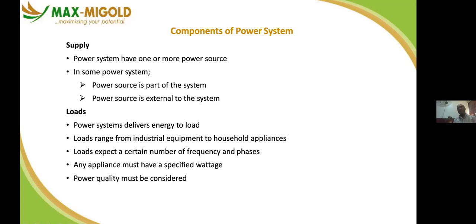Frequency also plays a major part in running your appliances. The power you are generating must maintain a certain frequency. In Nigeria, we make use of 50 hertz; in America, we make use of 60. It depends on the grid, which is standardized for use. So here in Nigeria, we make use of 50 hertz. Anything outside this range, between 49 and 52 or so, above or below, has an effect on your appliance. They will not work, or even if they are working, they won't work well. At times, they will not even come up. That's why you need to pay attention to the frequency of what you are generating.